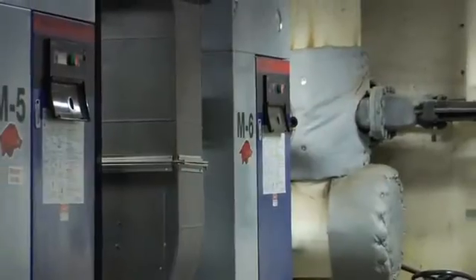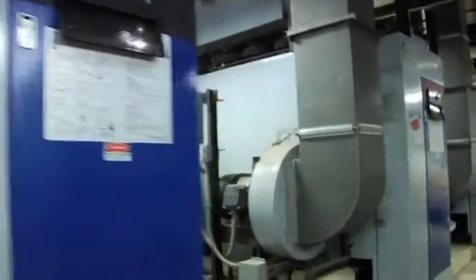The efficiency level that the Miura brings to the table is beneficial in energy savings, and it allows us to better meet the demand of the school between one season and the next. We're saving something on the order of about $200,000 a year in gas cost. This is 24/7 — most people shut their boilers off in the summer, but we don't. We're running to maintain domestic hot water in the buildings, so they're running all the time. To date with the project, we've saved approximately 1.3 million pounds of CO2 that would have gone into the environment as a result of installing the more efficient Miura boilers. It's certainly helped us move towards achieving our greenhouse gas objectives here on campus.